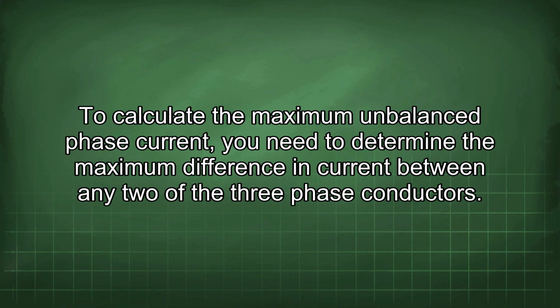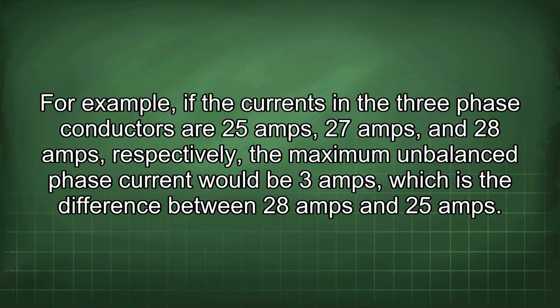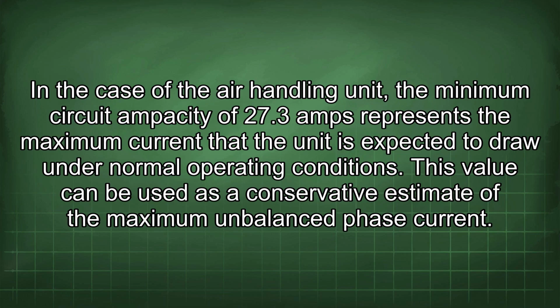To calculate the maximum unbalanced phase current, you need to determine the maximum difference in current between any two of the three-phase conductors. For example, if the currents in the three-phase conductors are 25 amps, 27 amps, and 28 amps respectively, the maximum unbalanced phase current would be 3 amps, which is the difference between 28 amps and 25 amps. In the case of the air handling unit, the minimum circuit ampacity of 27.3 amps represents the maximum current that the unit is expected to draw under normal operating conditions. This value can be used as a conservative estimate of the maximum unbalanced phase current.